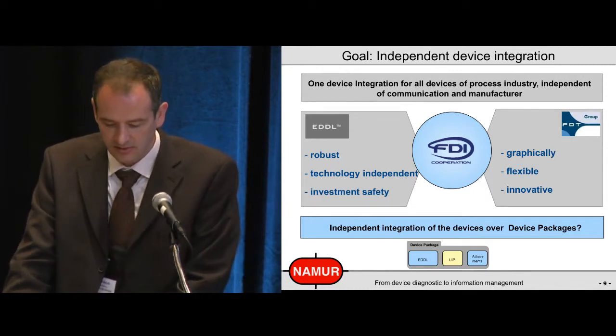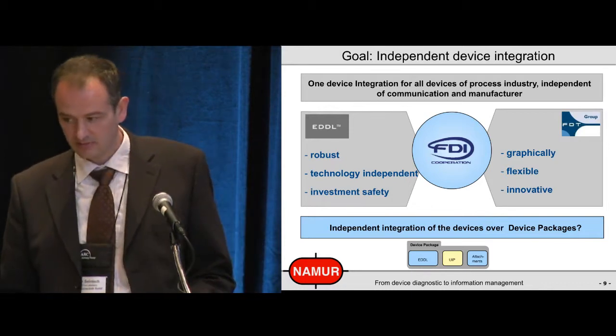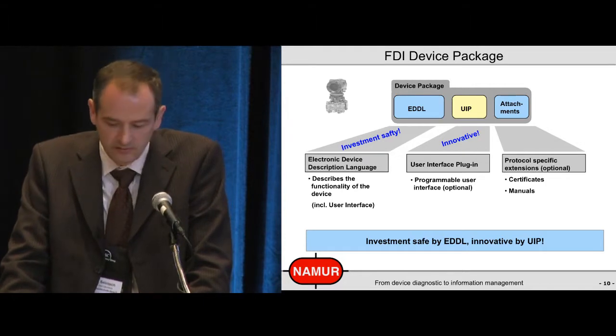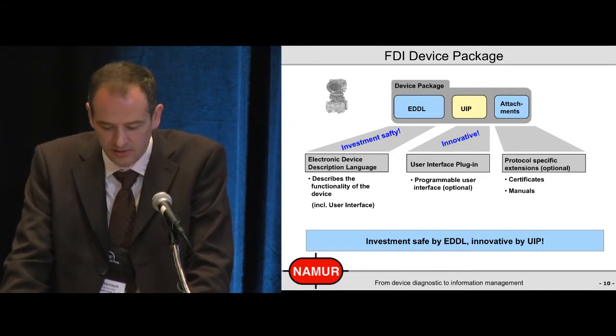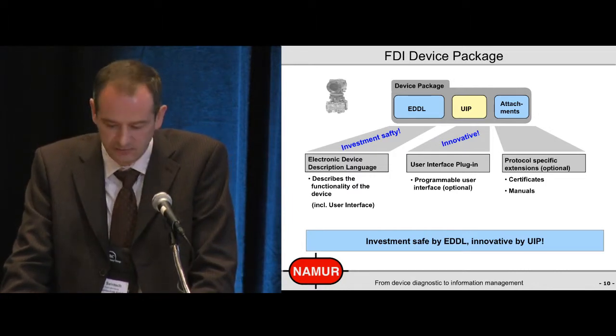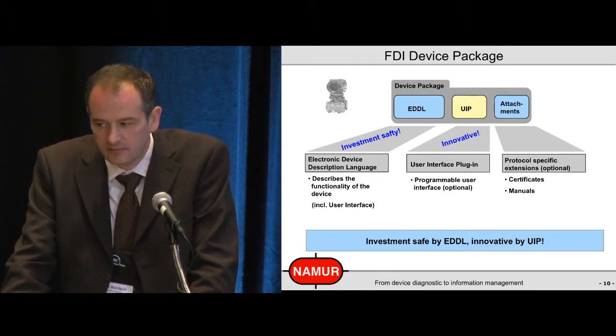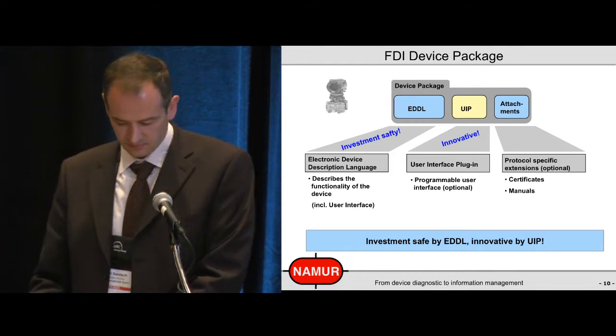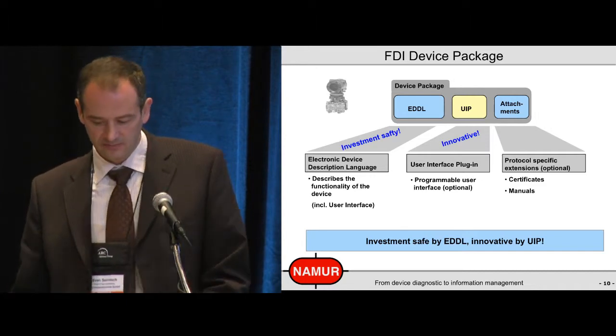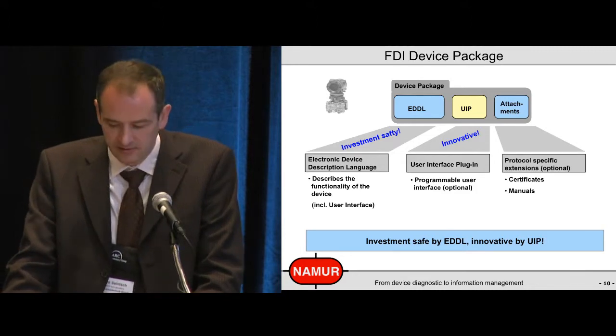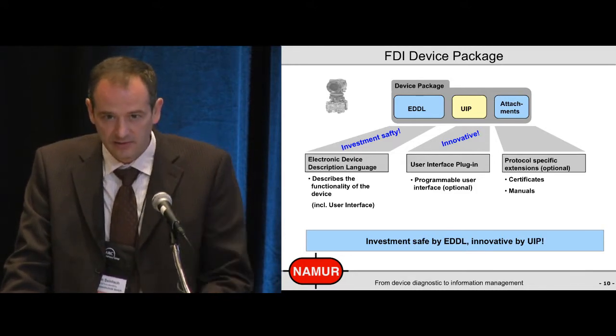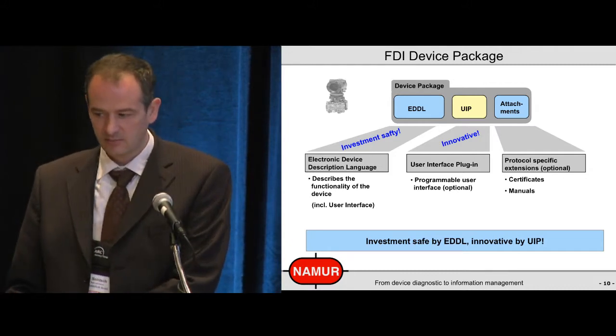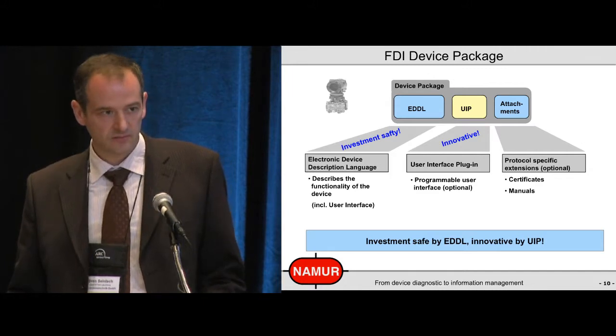This device package contains everything that is needed to configure a device. It's divided in three parts. It's an EDDL part that stands for investment safety and describes the complete functionality of the device including a small user interface. The second part is the UIP, user interface plugin — this is fully programmable; you can do all the graphics you want and it's very flexible. The third part is attachments where you can bring in certificates and also manuals to use the device. Then you have one package that contains really everything needed to use the device, reaching investment safety by EDDL and innovation by the UIP.